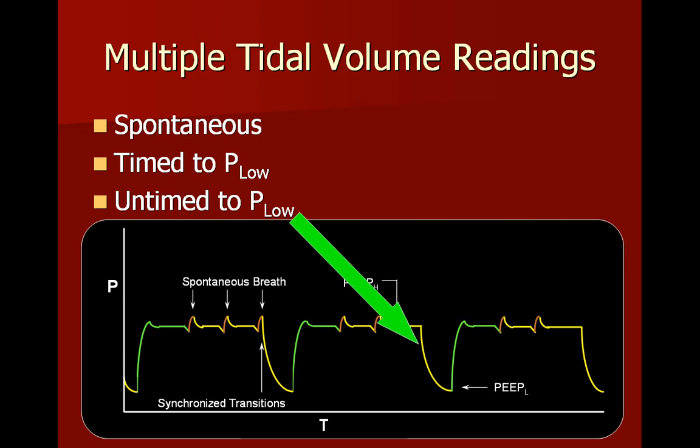Okay. What determines these last 2 is the delta pressure, the difference between P high and P low. This is where it might make a difference whether I set my P low at 0, my P low at 2, my P low at 7. Because that's going to be a bigger delta pressure to see. Now granted, it's not a lot of times per minute, 8 to 10, maybe 12 times a minute, that you're doing this drop, but that will make a difference in minute ventilation.